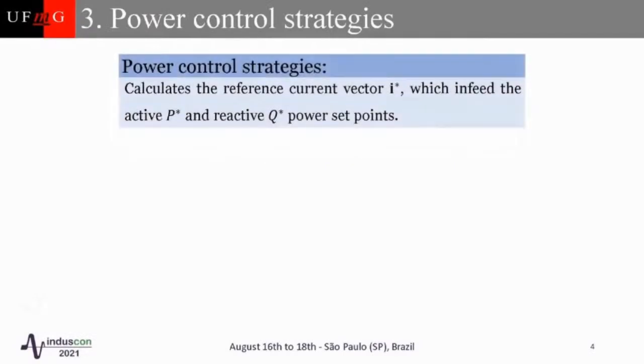Power control strategies are equations that allow calculation of the reference current needed to feed the grid the active and reactive power set points, and also make it possible to mitigate power quality problems. Different power control strategies can be described through the flexible approach.